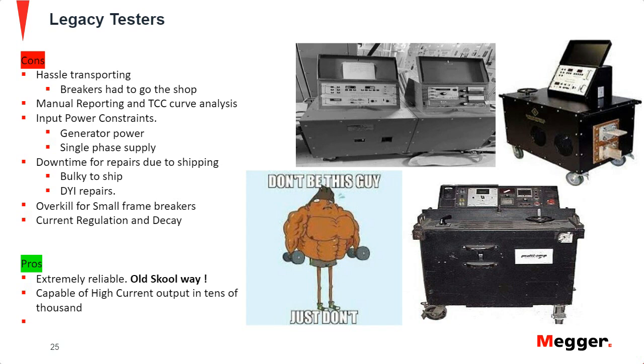However, they are extremely reliable. So again, you can run into issues with size, transportability, manual reporting, and then just being too big. But again, you'll never go wrong with having one of these test sets. These test sets were reliable. Everything manual as far as the variac, tap changer, everything like that. So very easy to teach on. Just again, not really transportable and not ideal when you're trying to get into those small switchgear rooms or into the data centers with these.